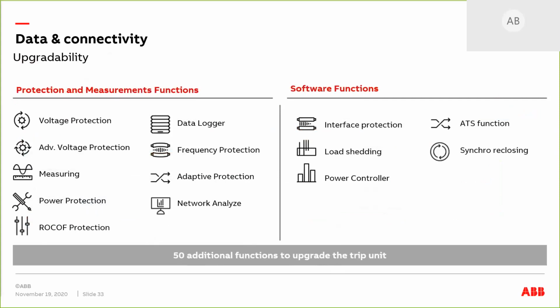So what software functions are we looking at? We're actually looking at the software function of interface protection. The interface protection can be done by the ACB and the MCCB. Load shedding capability can be done by both ACB and MCCB, the ATS, the synchro reclosing, and the power controller. By the way guys, for example the power controller, we will have to have an additional function in terms of our hardware.